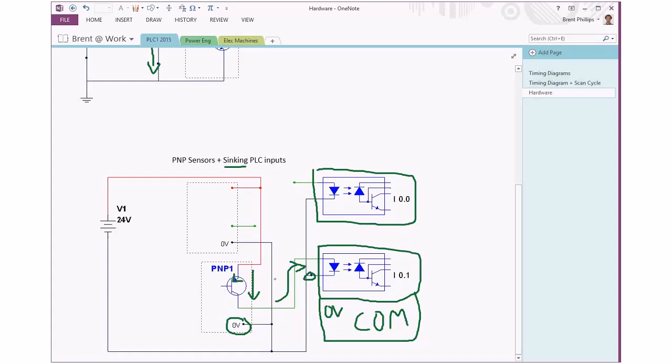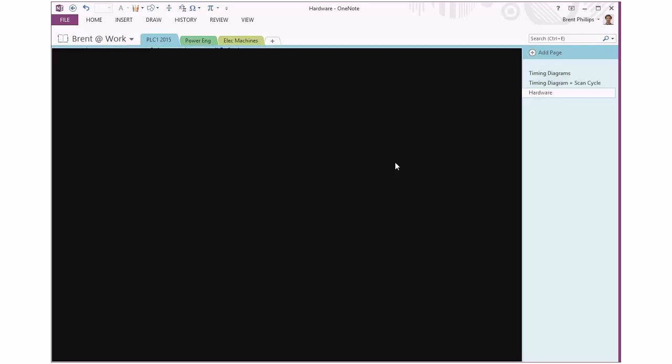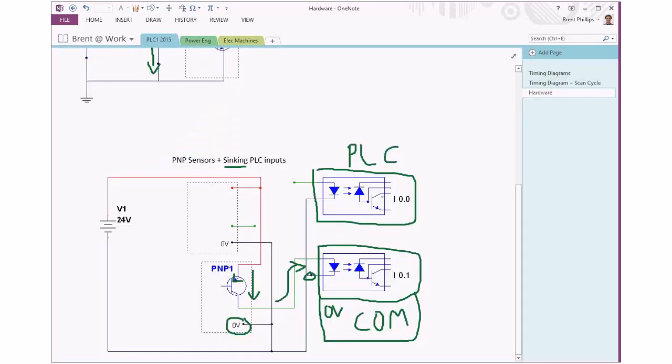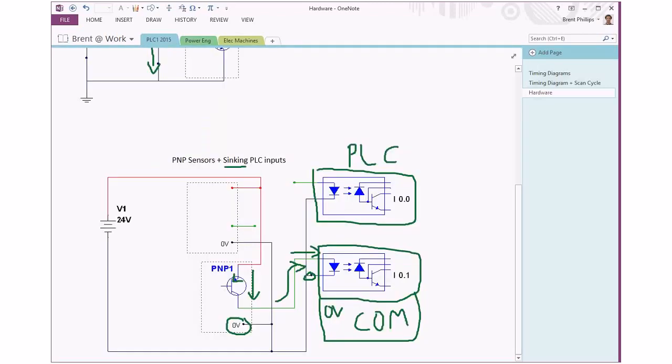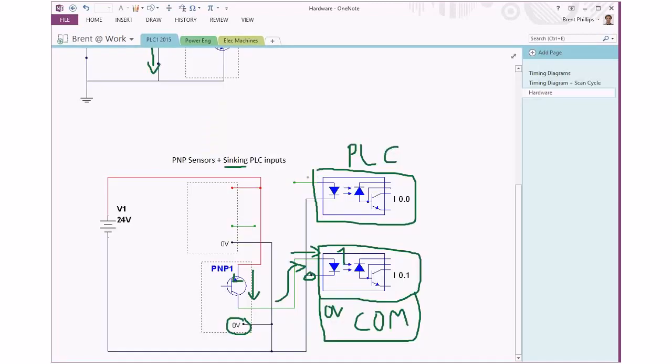So there's a key difference for us between using sinking and sourcing on our PLC. Remember, we've always got these separate parts. Our PLC circuit - if it's sinking, the current is flowing from the outside world into the PLC, into the numbered channels. There's number one here, the current's flowing into number zero.